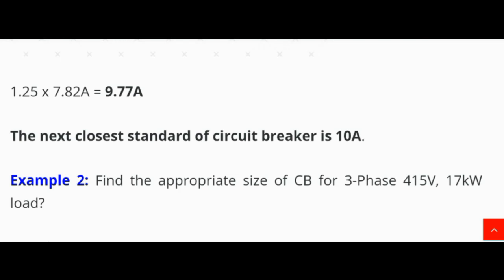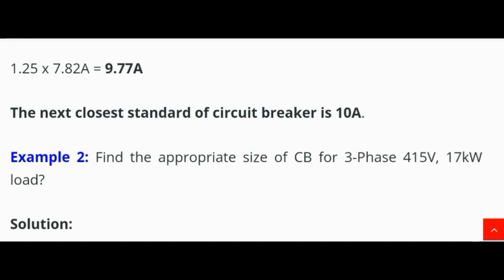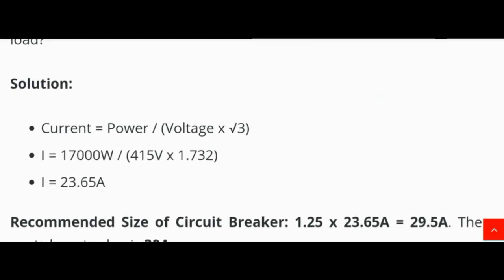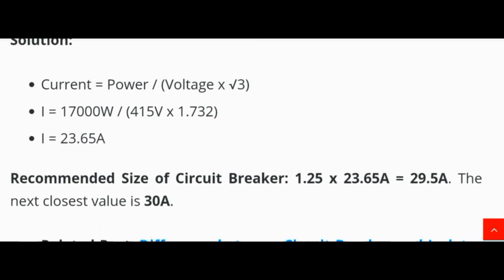Example 2: Find the appropriate size of circuit breaker for a three phase, 415 volt, 17 kW load. Solution: I = P / (V × √3) = 17,000 W / (415 V × 1.732) = 23.65 ampere. Recommended breaker size: 1.25 × 23.65 A = 29.5 ampere. The next closest standard value is 30 ampere, so we will use a 30 ampere circuit breaker.